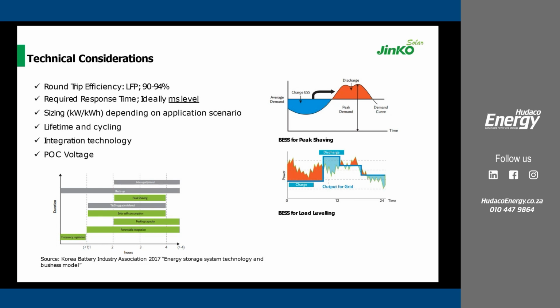In some scenarios, especially those with diesel generators and an ATS switching between off-grid to on-grid, you'll find that the switching time is usually in the seconds level, typically between 1 to 45 seconds, which in some manufacturing settings might not be convenient, because it may result in stopping production. For example, in plastic manufacturing, which is very sensitive to power supply and the running of equipment.